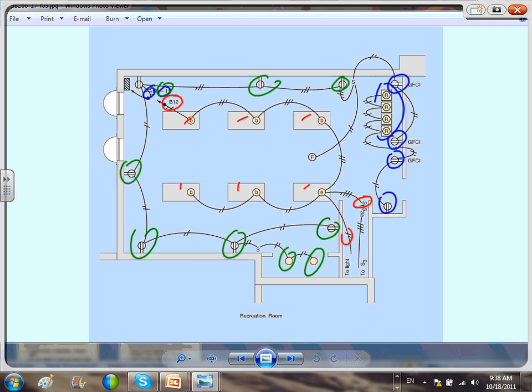How many receptacles do I need on a sink, on a bar? As many as you want. This is not a kitchen. The 2x4 rule does not apply. Not a kitchen. So it's a good idea, guys. If I were you, I would apply the same rule as for the kitchen. What's the rule for the kitchen? 2x4, 2 from every opening, 4 in between. Good idea. If you have a bar, you have a reason for having a bar, right? To entertain, you do a lot of other stuff. Any question, guys, about these? How they circuited? They used a multi-wire branch circuit.